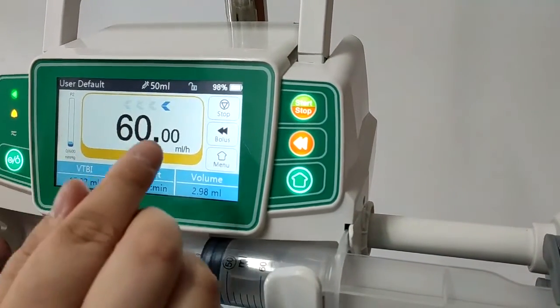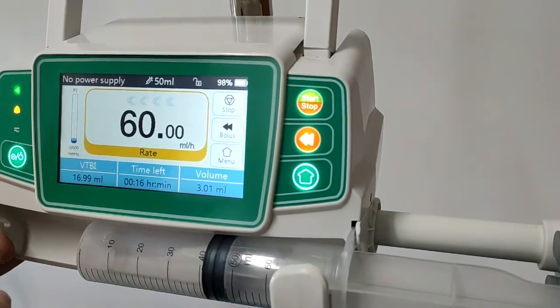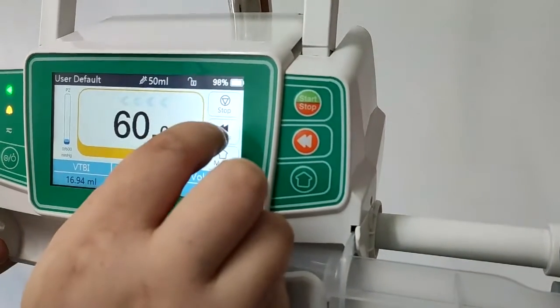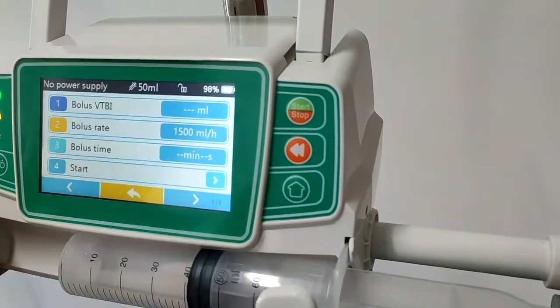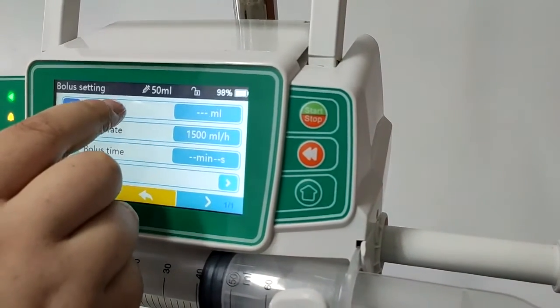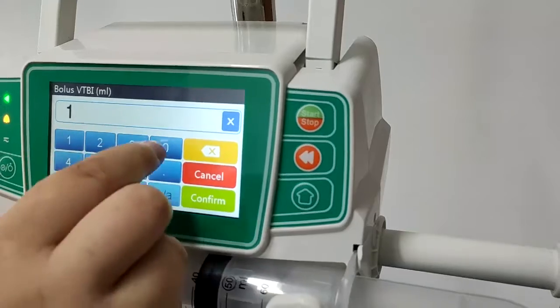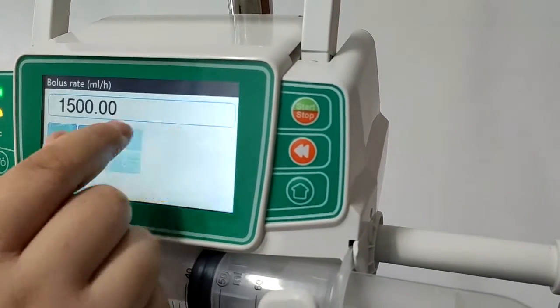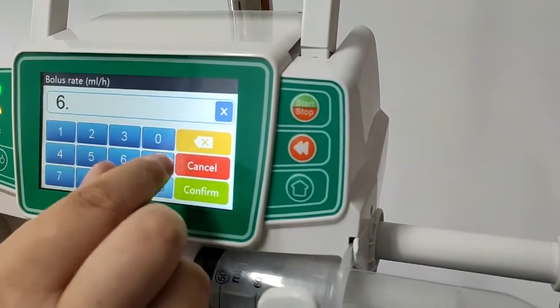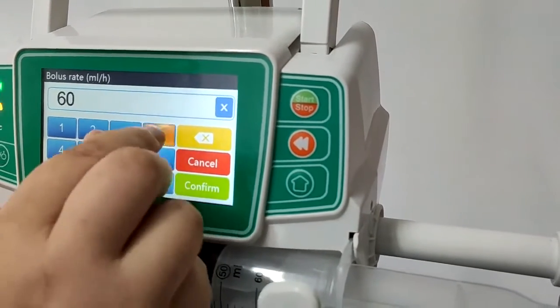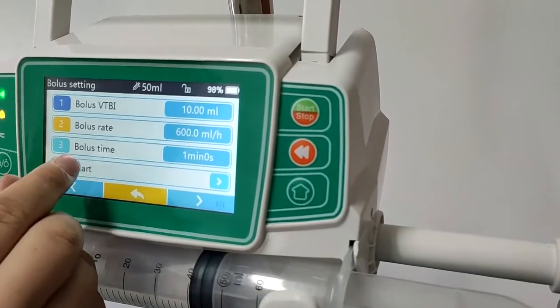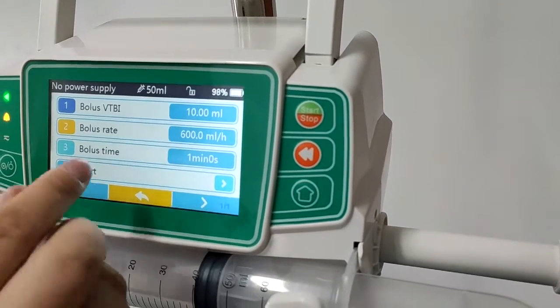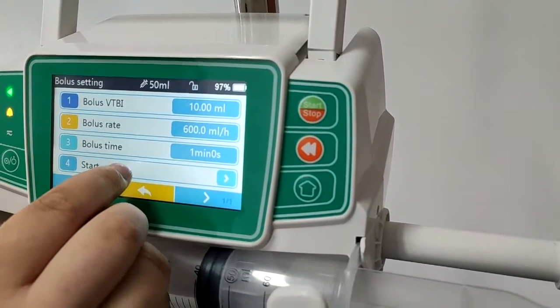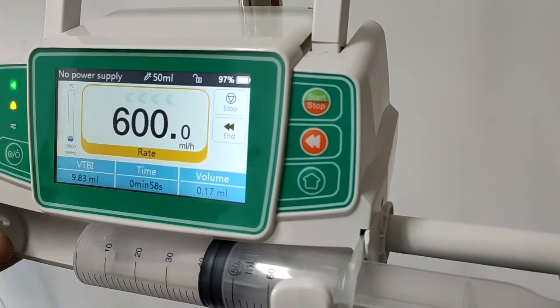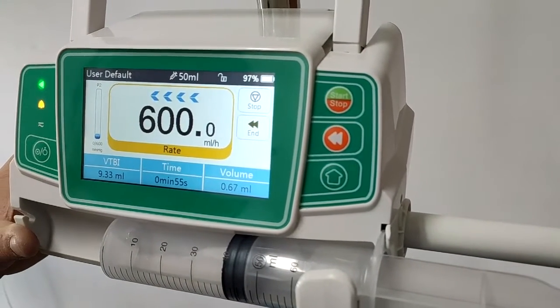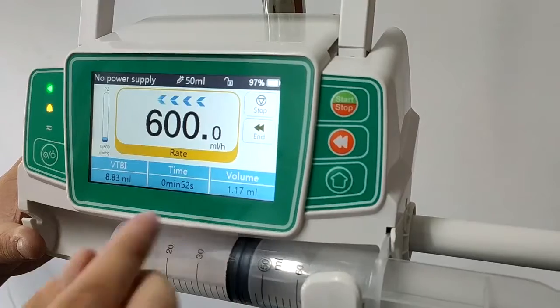The second is automatic or programmable bolus, by pressing the software bolus key. Here you can set the bolus VTBI, like 10 ml, and the bolus rate, maybe 600 ml per hour. The bolus time will be calculated automatically. Press start, and it will start the automatic bolus. It also beeps every 1 ml.